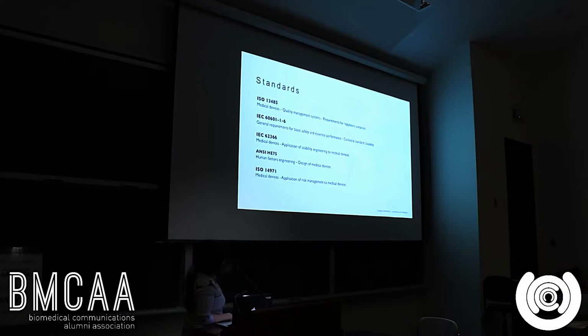And here's a brief list of examples of the standards we do consult and follow. The top one is, overall, if you ever wanted to develop a medical device from scratch, what you really, really, really need to know. All the others below follow it, but they talk about specific things like human factors engineering, usability engineering, and risk management for your device. One interesting one is the HE75. If you're ever designing a UI for your device, it has a lot of specific information like contrast and font sizes to use.